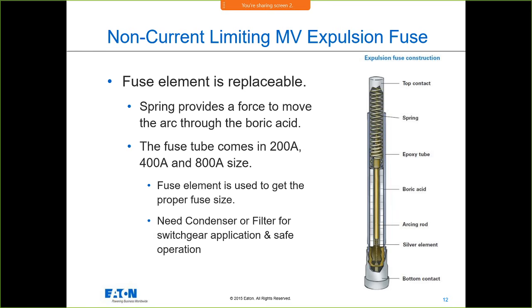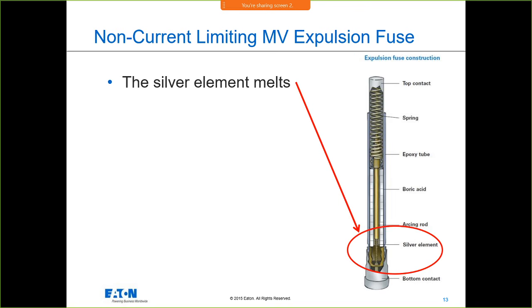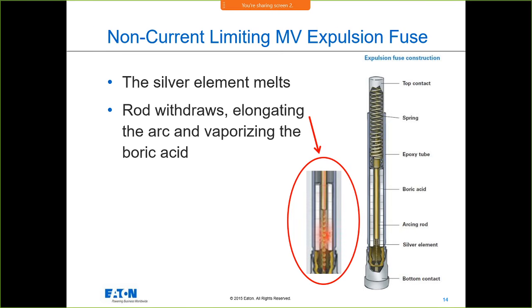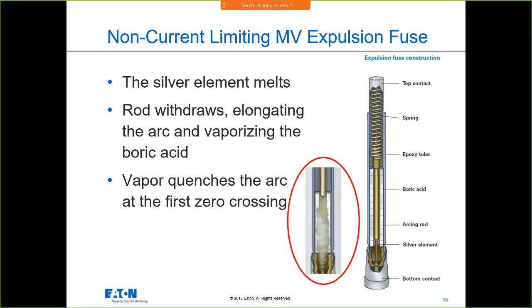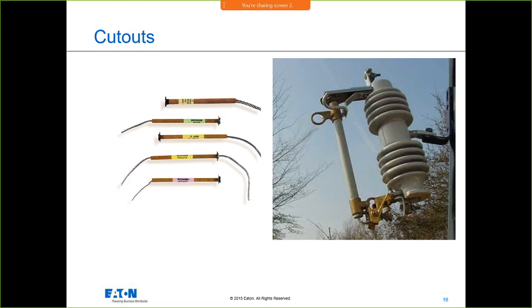Basically, you have the amp sizes, and because these are medium voltage, you're not going to have a 6,000 amp fuse. They're going to be relatively smaller, and you have that silver element that will melt down on the bottom. The rod is going to withdraw and elongate the arc, letting the boric acid do its job and extinguish it inside of that tube. You'll see these up on poles and in the cutouts. You can replace these things.